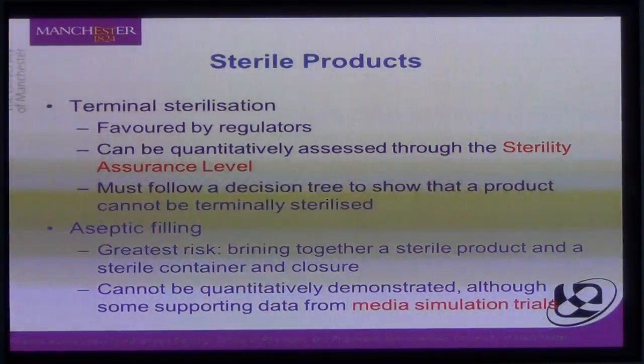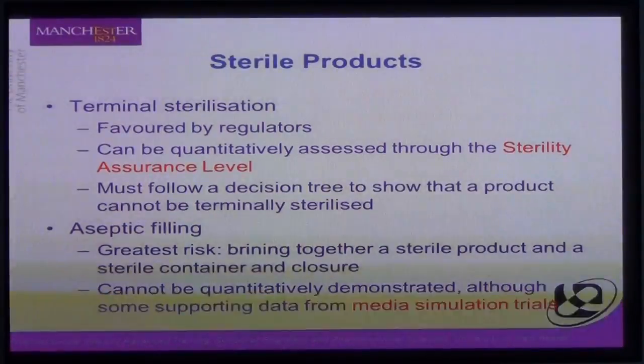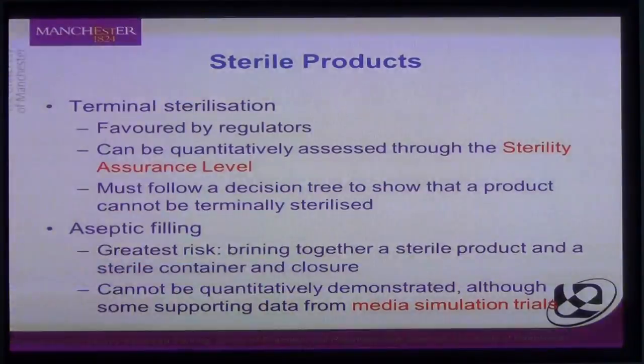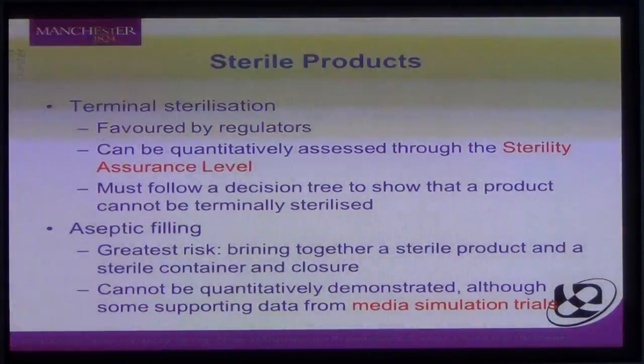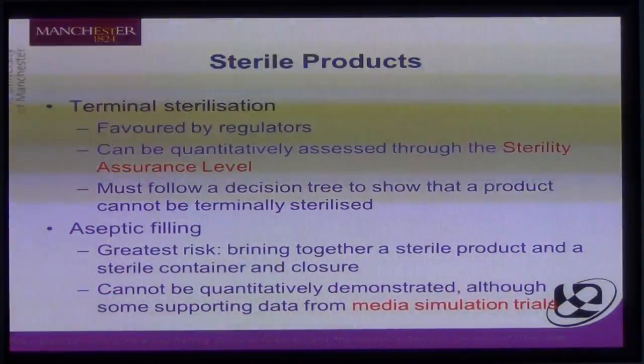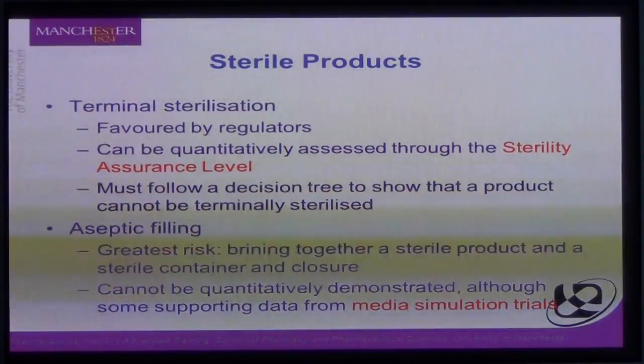Terminal sterilisation is naturally preferred by regulators because we can quantitatively assess it through the concept of the sterility assurance level. Regulators require that terminal sterilisation is the method of choice — you must use it unless you can prove that your product wouldn't survive the process, in which case you can proceed to aseptic filling, but a rationale or justification is required. Aseptic filling is a greater risk.